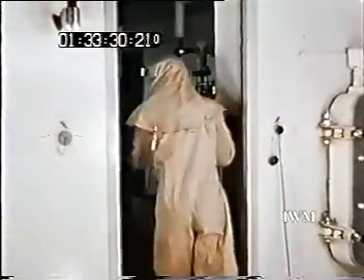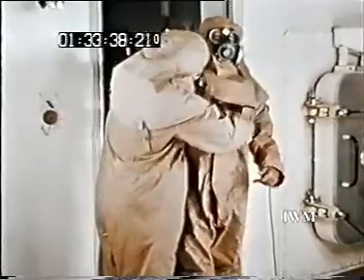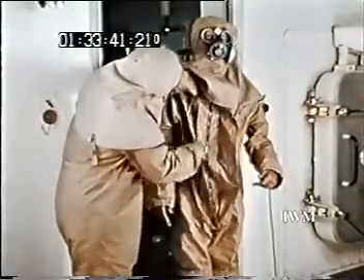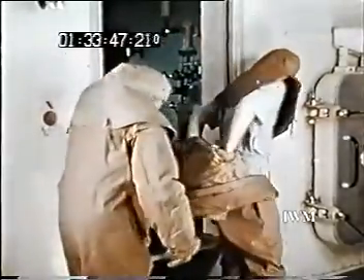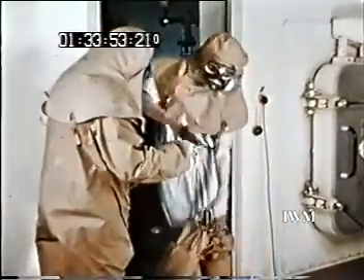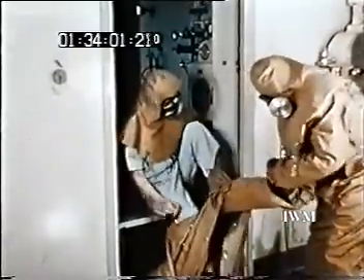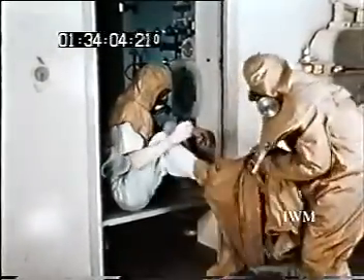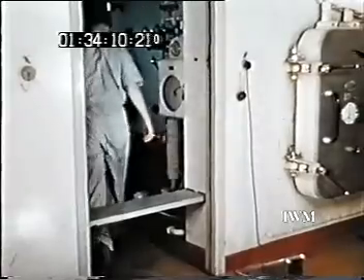Now we see how the team undress to leave the laboratory. This method has been adopted to minimize the hazard involved. The controller, who has not been directly involved with samples or animals, assists each member to undress. The person undressing does so in such a way that avoids contaminating the seat and himself. Since the laboratory is being ventilated by air drawn in through this doorway, there is quite a strong current of clean air passing through at this position. He enters the autoclave room, removes his inner suit, and then takes a shower before replacing his normal clothes.